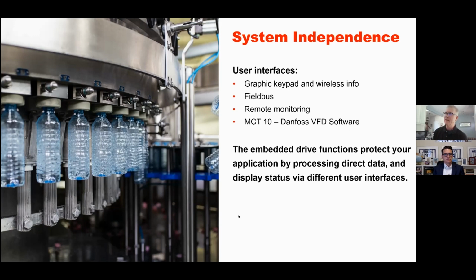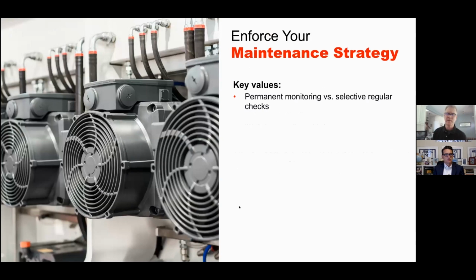What are the key values? Permanent monitoring versus selective regular checks. Again, this is a big thing because you're getting real live data 24/7 versus a spot check once, whenever your PM program is, quarterly, weekly, monthly, that type of thing. You're transitioning from a scheduled maintenance program to a condition-based maintenance program.